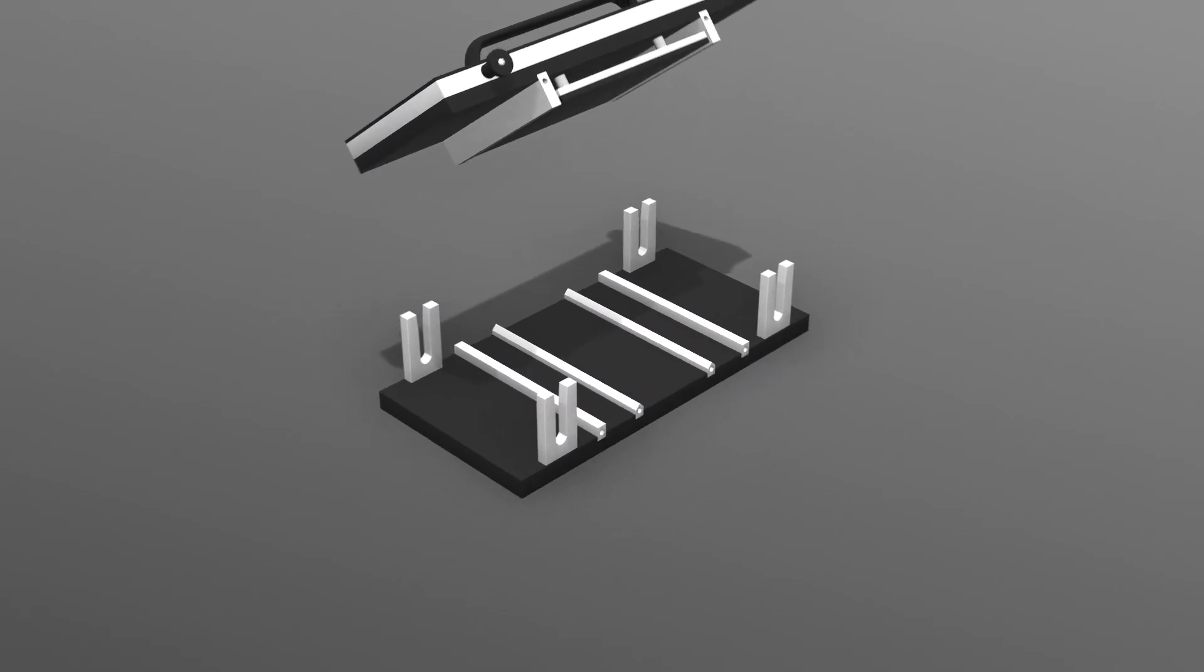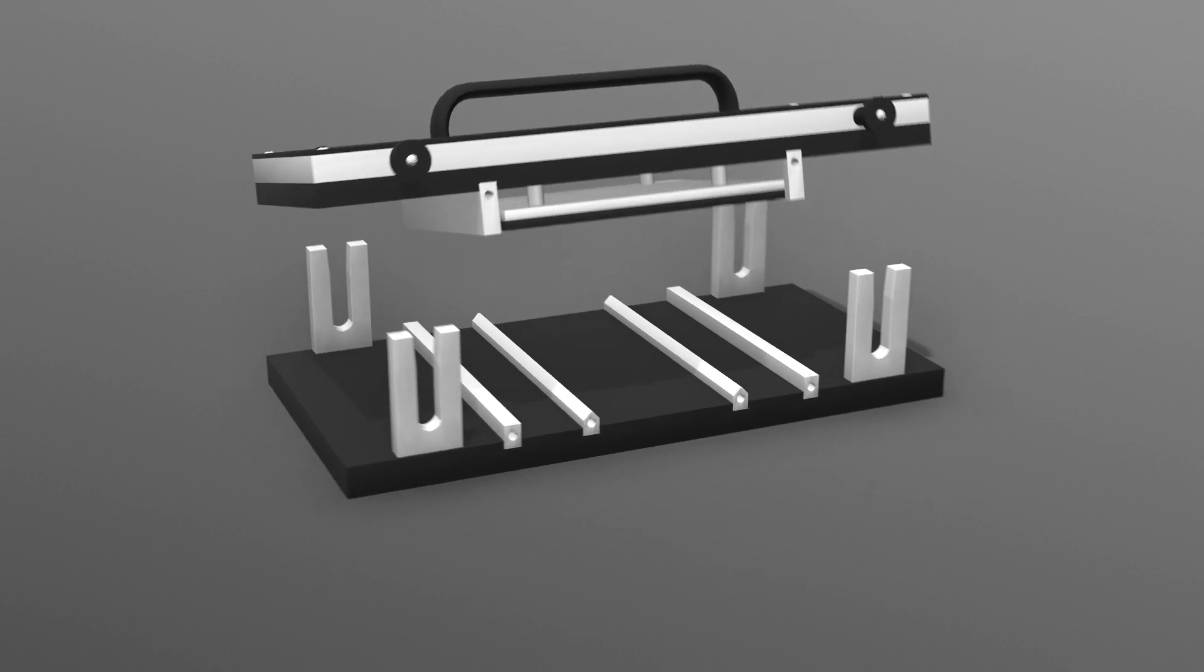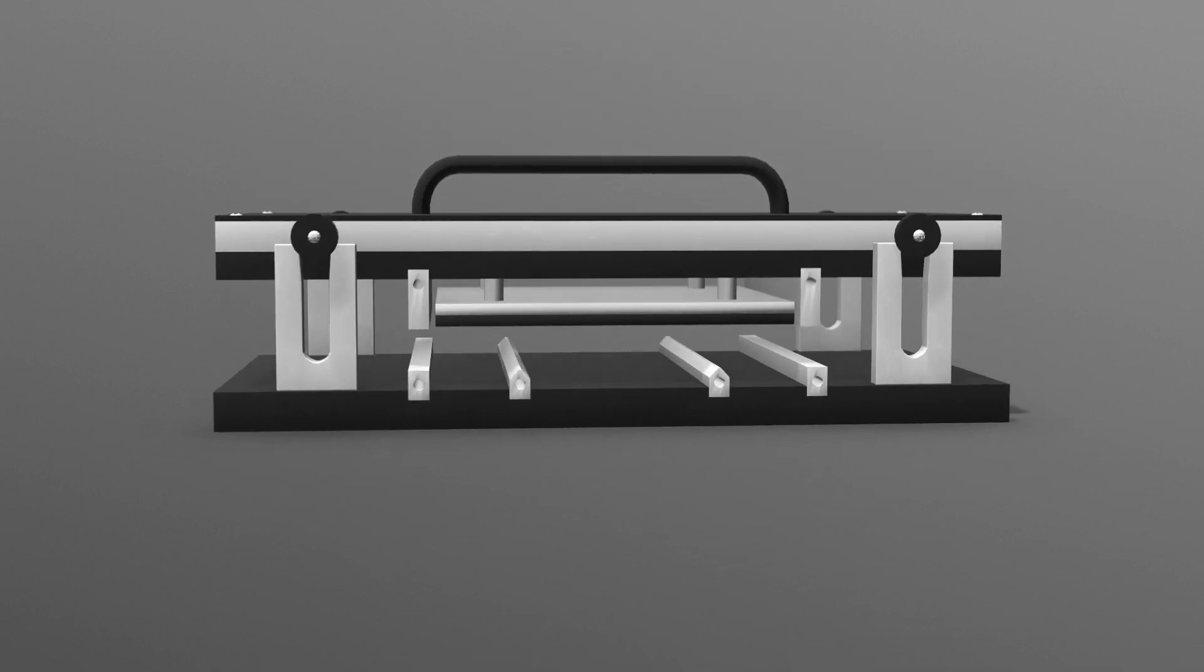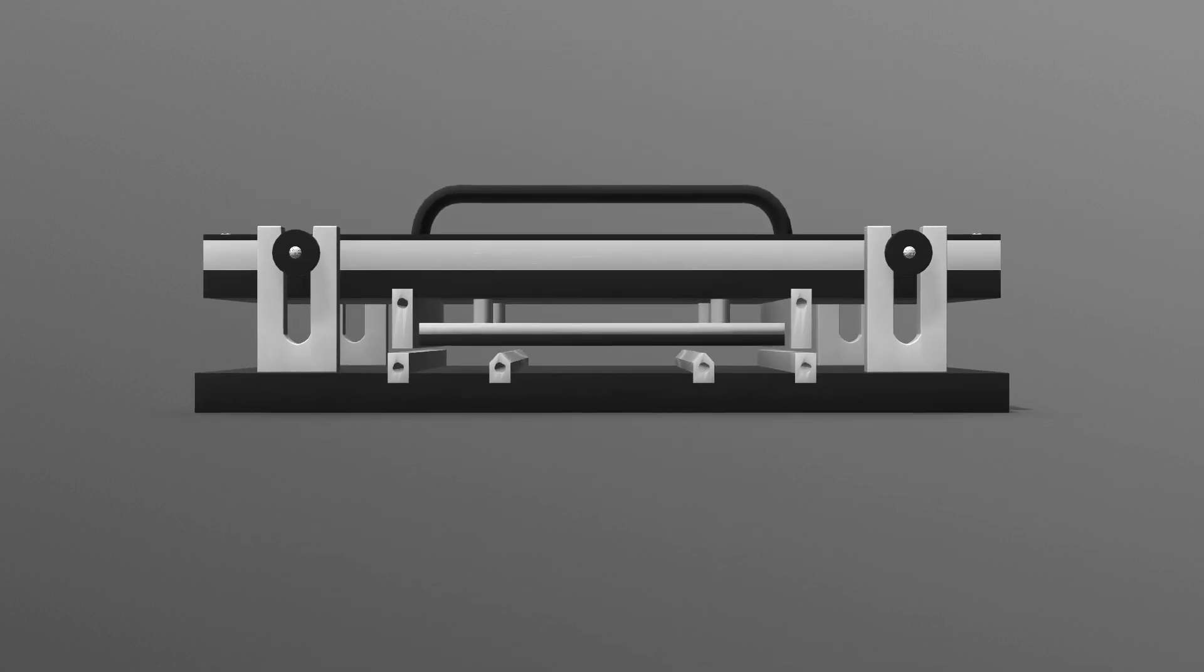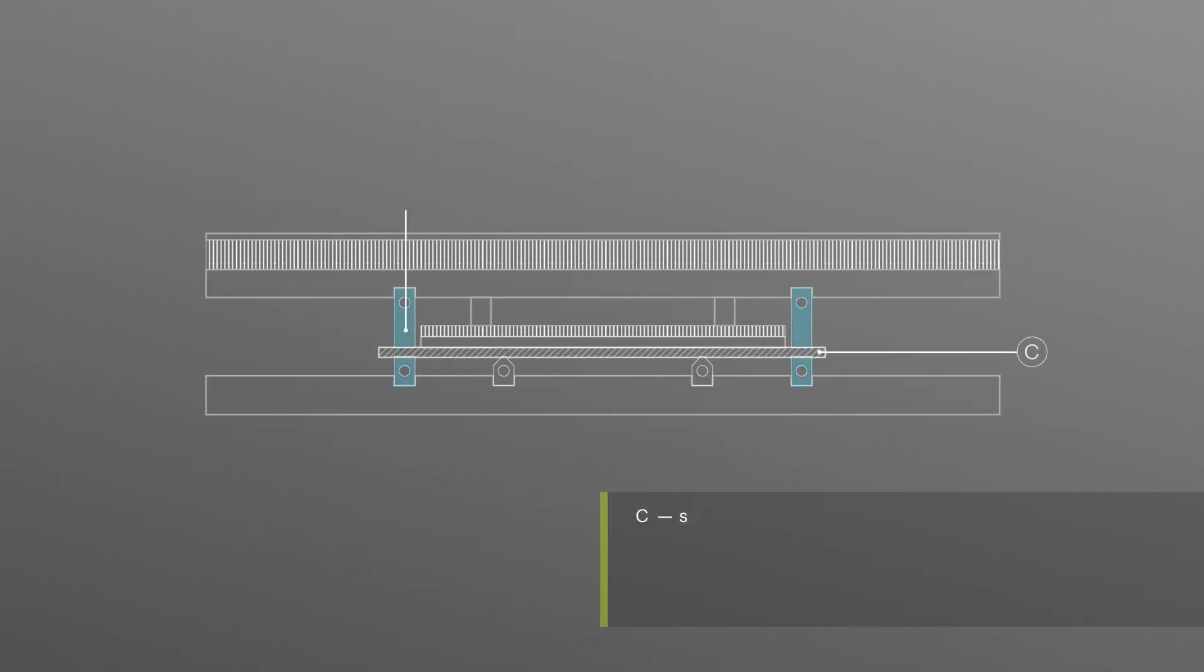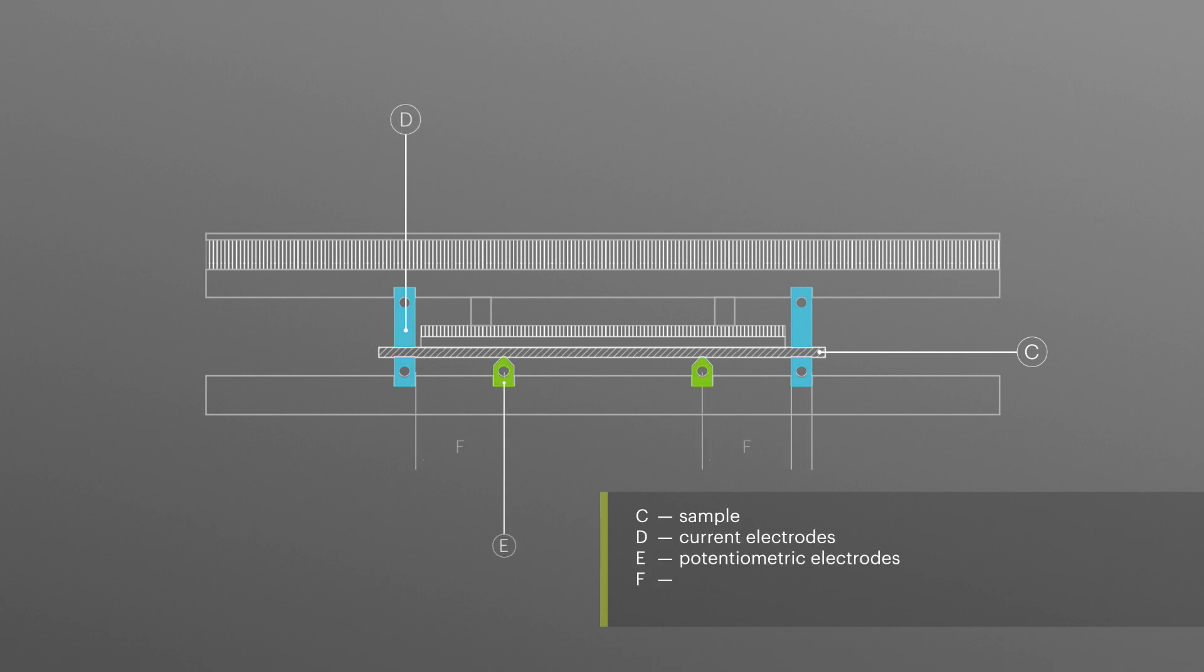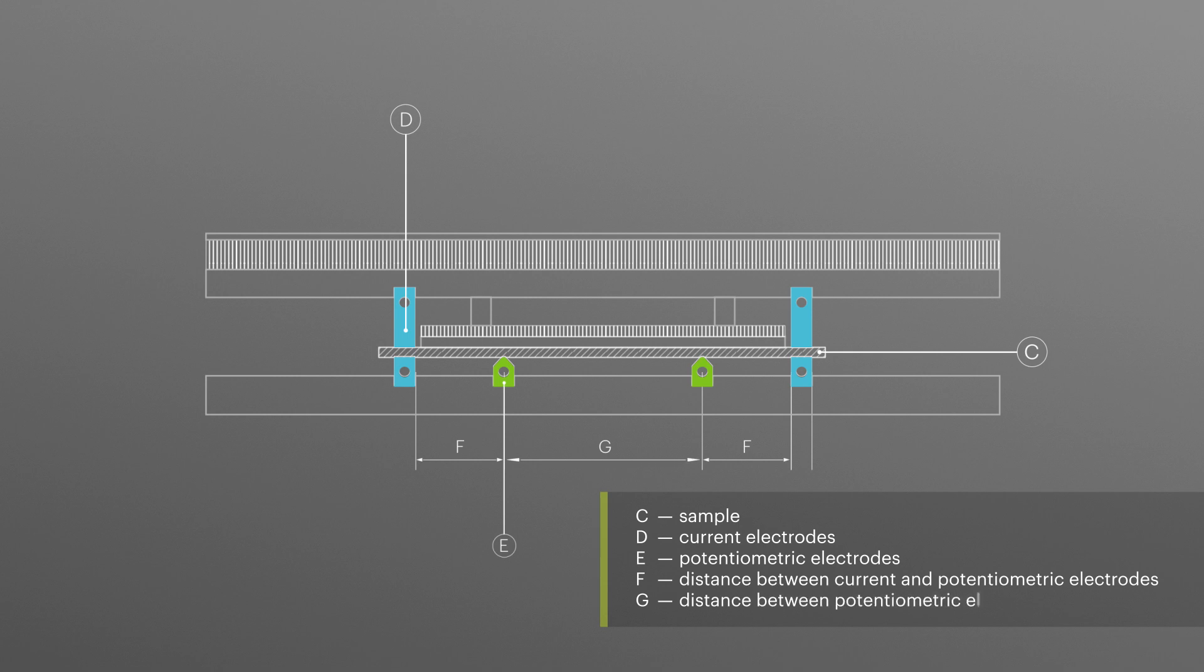The measurement uses two pairs of identical current electrodes, with one pair attached under the sample and the other pair attached above the sample directly above the first pair. A pair of potentiometric electrodes is secured in such a way that all the electrodes are in a straight line and their upper surfaces are in the same horizontal plane.